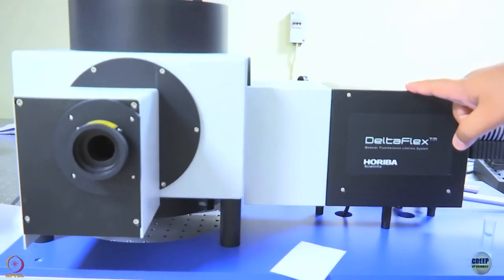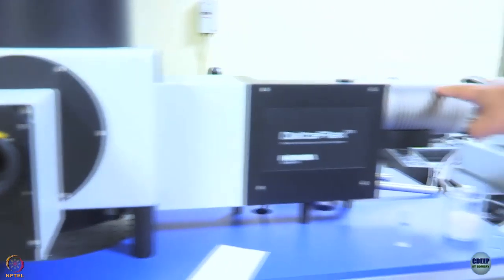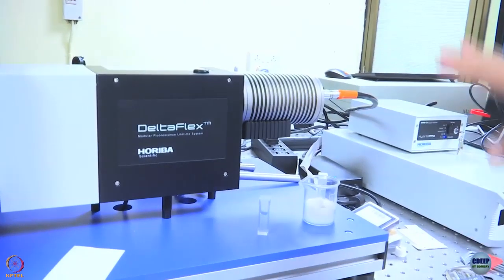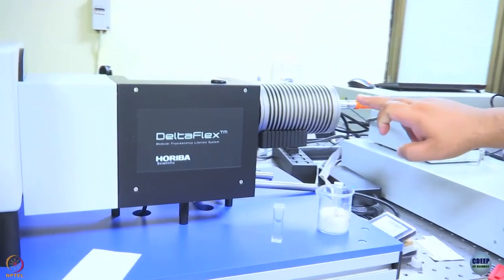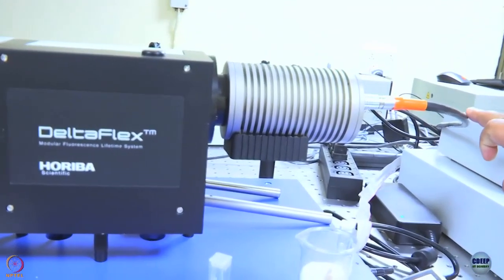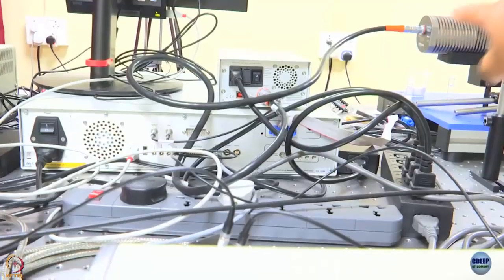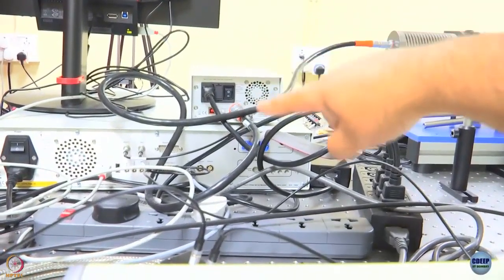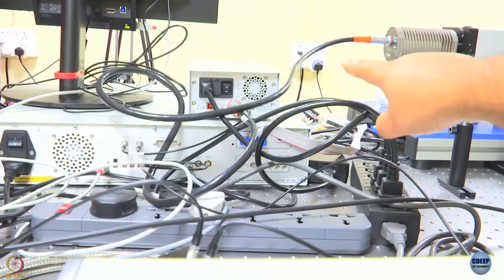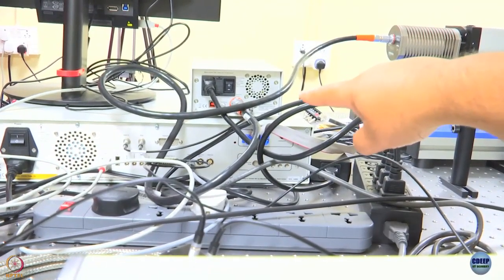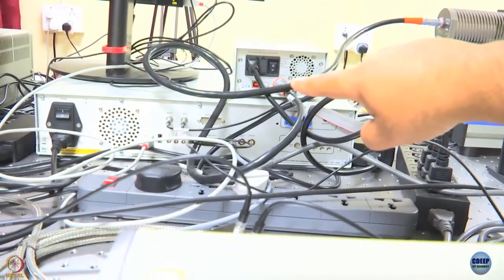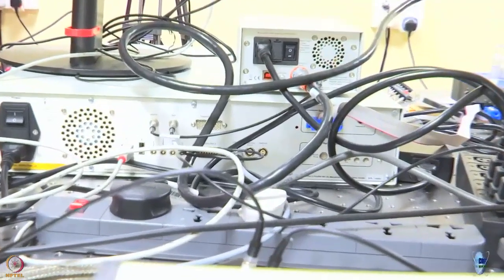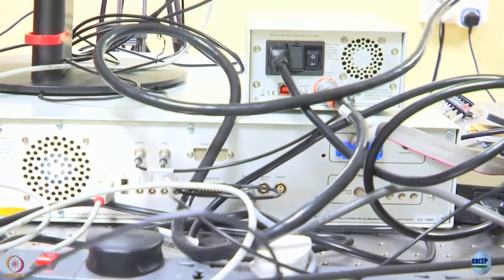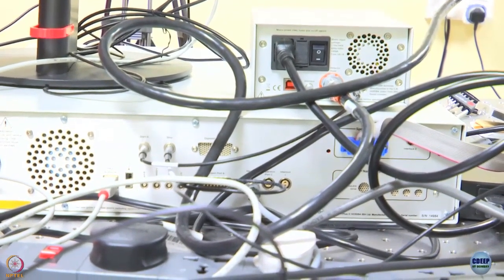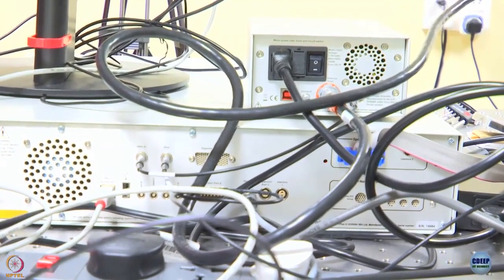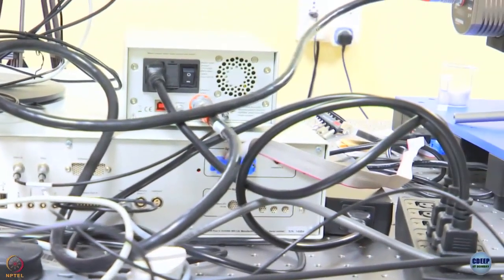Here we have a monochromator which we have discussed in the theory class, and this is a fast detector that we have. It is a new kind of hybrid detector, and you can see the output of the detector goes through this thick cable. It has come out and gone to a small box there. From there, a small cable comes out and goes into a terminal called start A. That is the start of the time to amplitude converter that we have discussed in the previous class. And before going there, inside that small box itself, we have the constant fraction discriminator.